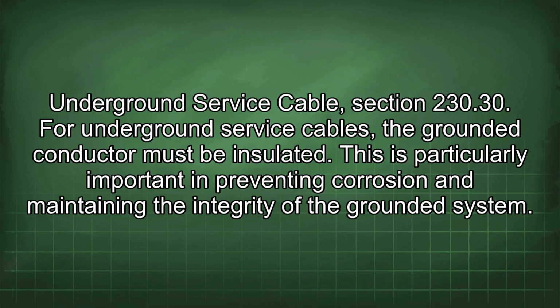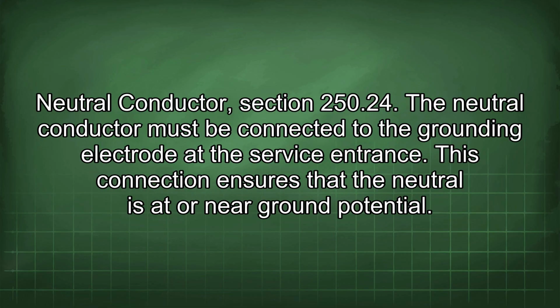Underground service cable, section 230.30. For underground service cables, the grounded conductor must be insulated. This is particularly important in preventing corrosion and maintaining the integrity of the grounded system. Neutral conductor, section 250.24. The neutral conductor must be connected to the grounding electrode at the service entrance. This connection ensures that the neutral is at or near ground potential.